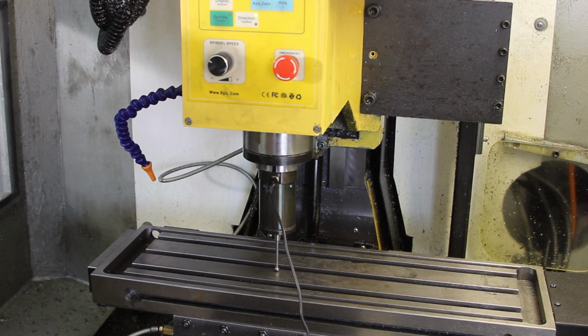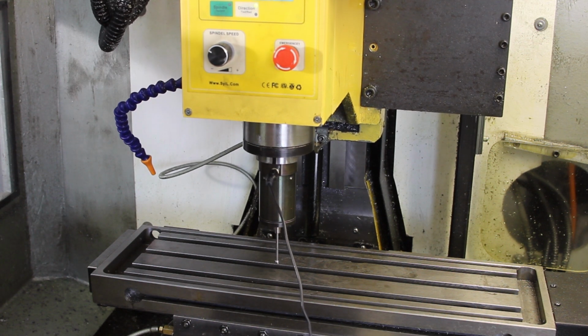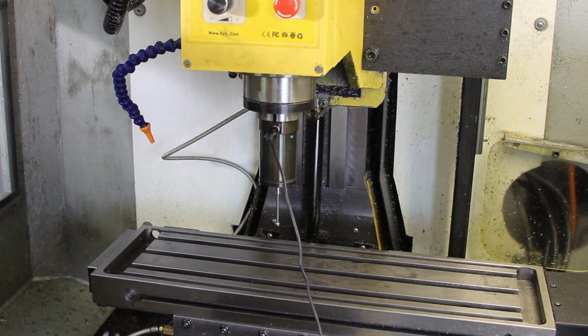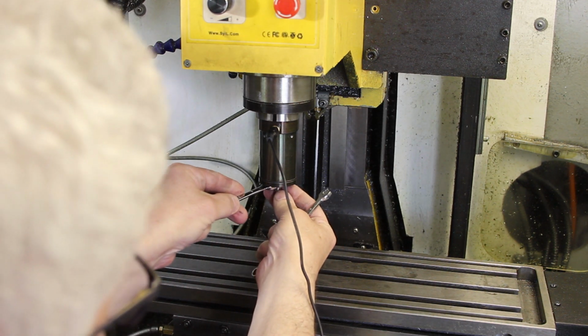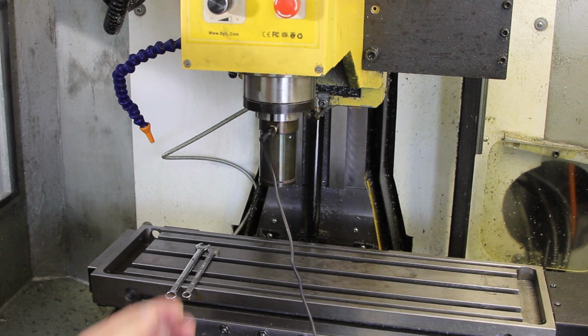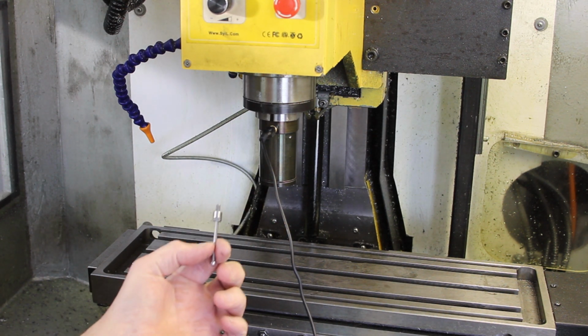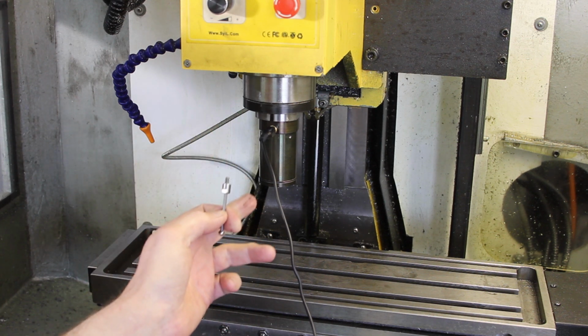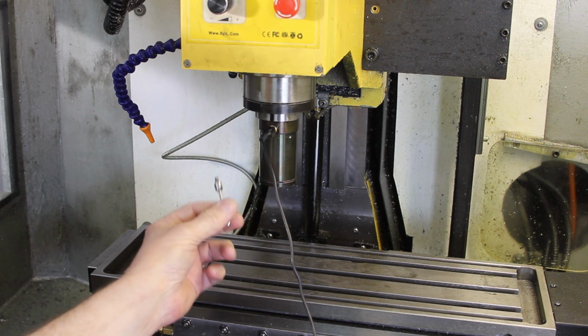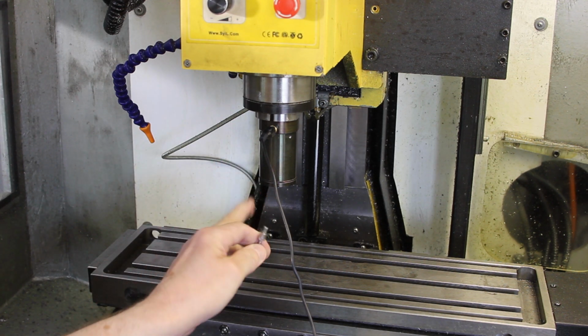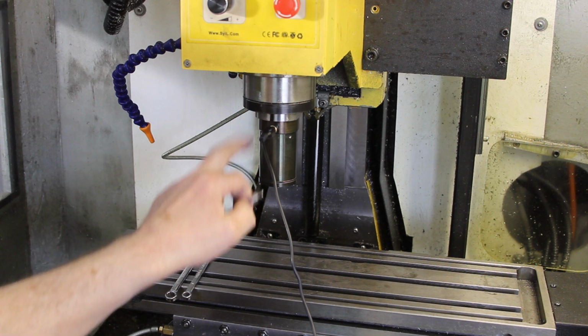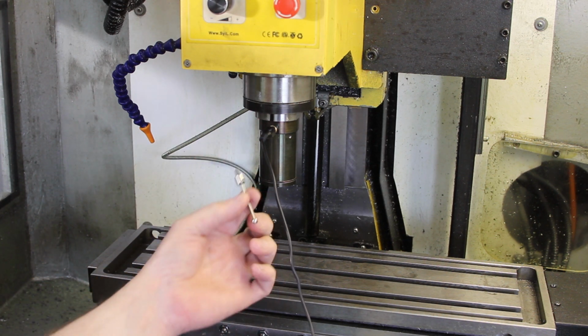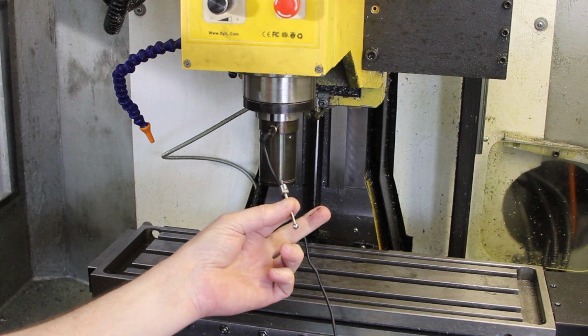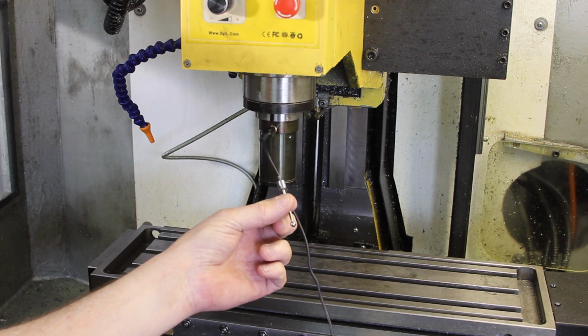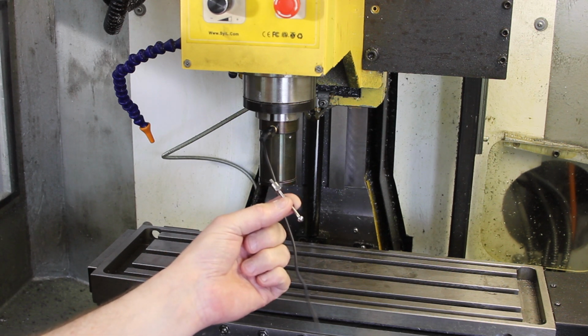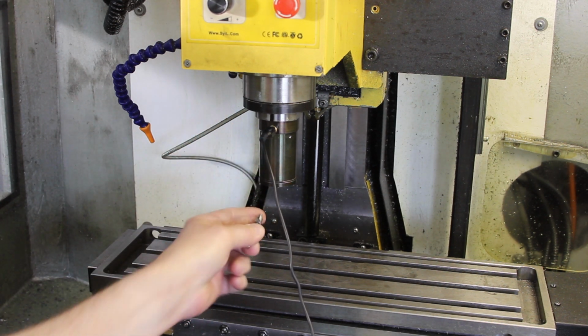I am going to jog up and take the probe off. And you might think, why am I doing that? Because I'm going to repeat that test without the probe on. So the net result is subtracting the length we've just set from the length I'm just about to set will tell us exactly how long this probe is. But more importantly, it will tell us exactly how long this probe body is. So that when I replace the next probe, because I'm going to make some other types of probe, all I'll need to do is enter, add the length of the new probe to the length of the body, and I don't need to do this test each time.